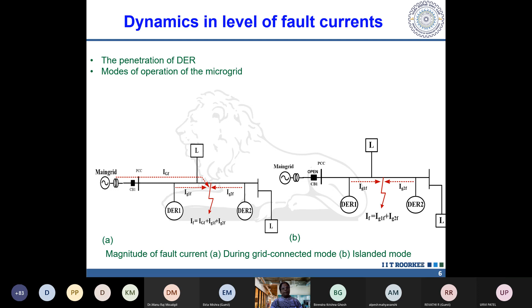Earlier what we used to do, we mention conventional relays, we maintain a single fixed setting, a static mode of operation. But from this small example I demonstrated in front of you, if your renewables are only present, I have not kept any battery or electric vehicle over here, that means every time our fault current magnitude and angle are modulated, I mean they change from time to time. So to accommodate this changed, dynamic scenario of the fault current behavior, we also have to make the relay setting dynamic. That is called adaptive.